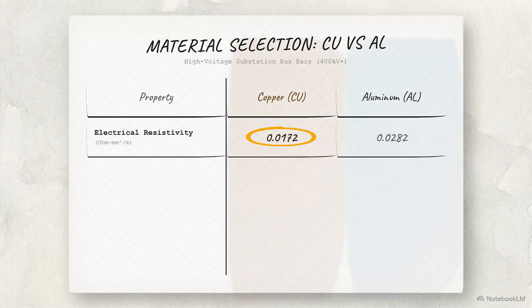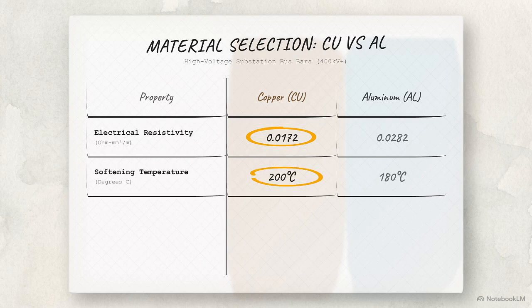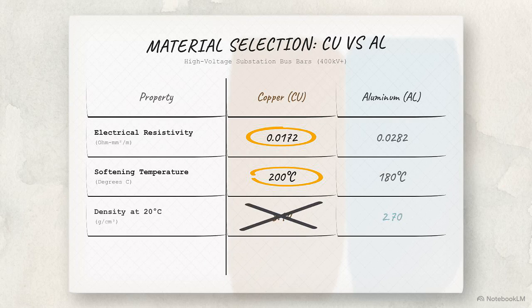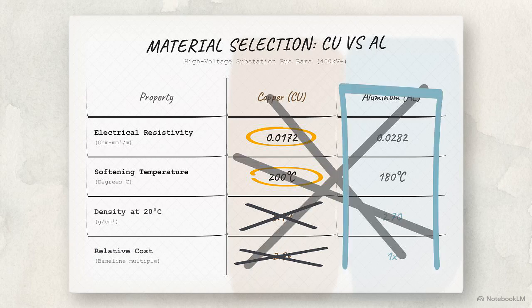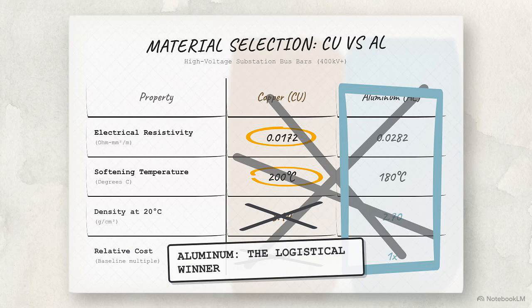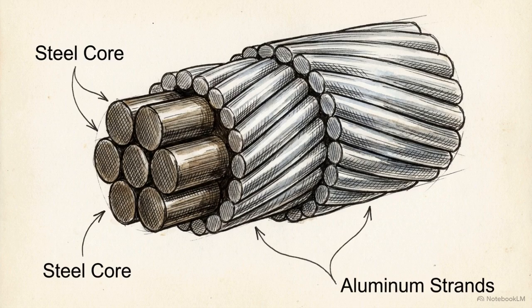Its electrical resistivity is much lower, at 0.0172 ohms, compared to aluminum's 0.0282, and it boasts a higher softening temperature of 200 degrees Celsius. But physical and economic deal breakers dictate the decision. Copper is nearly 9 times as dense as water, and 2.7 times more expensive than aluminum. Suspending hundreds of tons of copper high in the air is structurally punishing and financially prohibitive. Because of this mass-to-cost ratio, aluminum is the industry standard. Power Grid specifically mandates ACSR quad Bersimis or Moose conductors for their massive 400 kV main busbars.